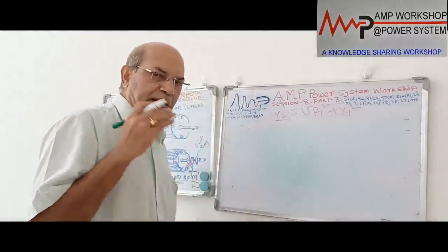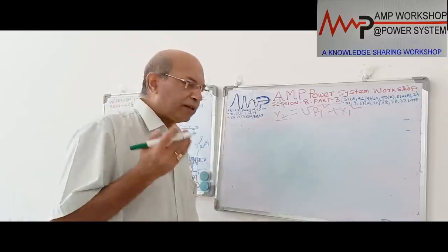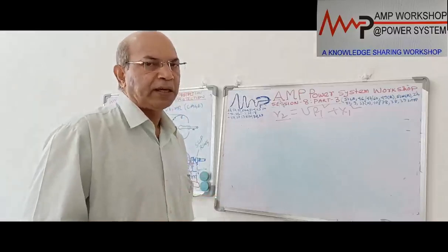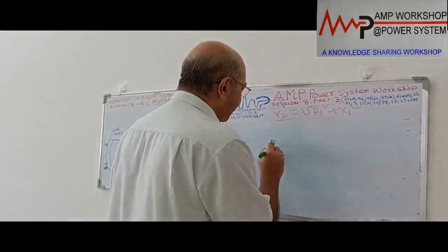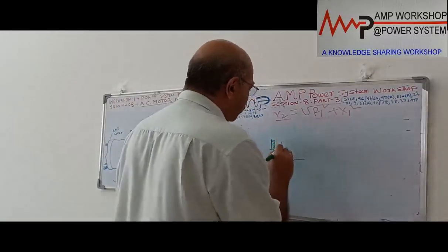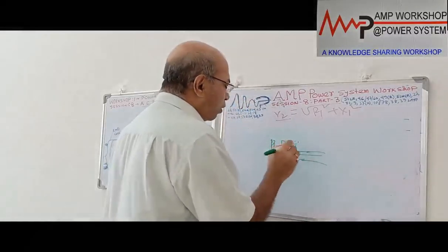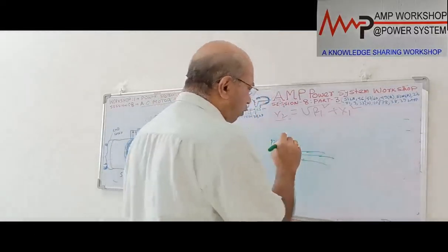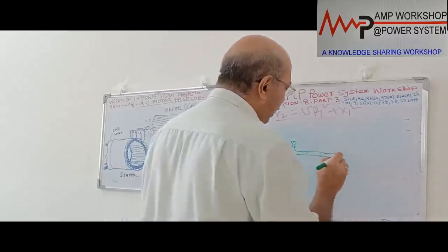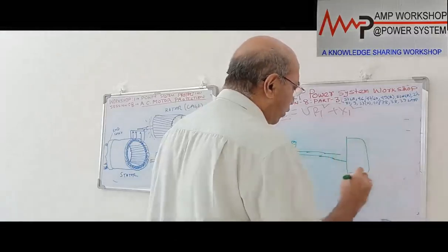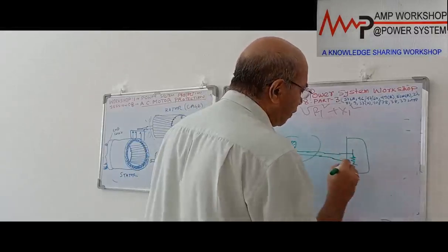At a particular temperature, the bearing RTD has a certain amount of resistance. If the bearing temperature goes up, then automatically the resistance will change. And that resistance value we can use in the same way. Suppose this is a bearing RTD, and this RTD is coming. Suppose there are two or three bearing RTDs, and they are coming to a junction box. Normally we put one RTD in each bearing, normally two RTDs on the two bearings. These RTDs are coming to a junction box, and they have some resistance. That means the bearing temperature is ultimately converted to an equivalent resistance value.